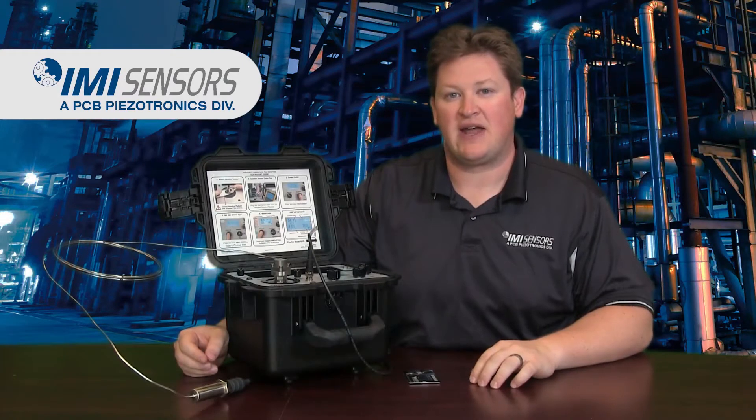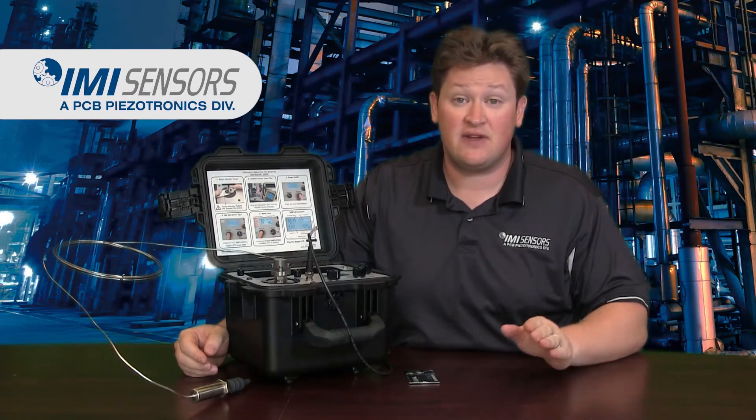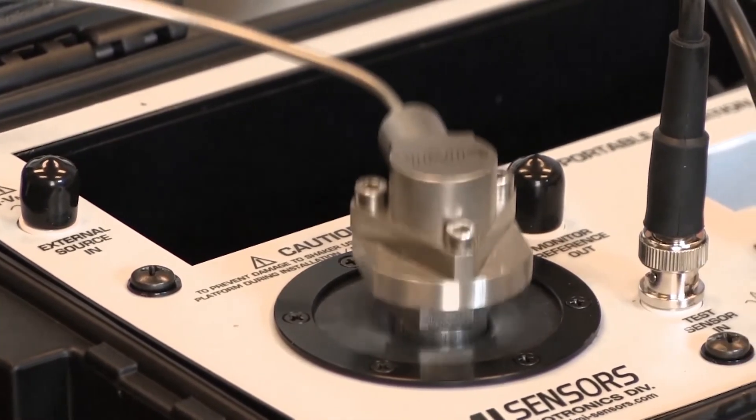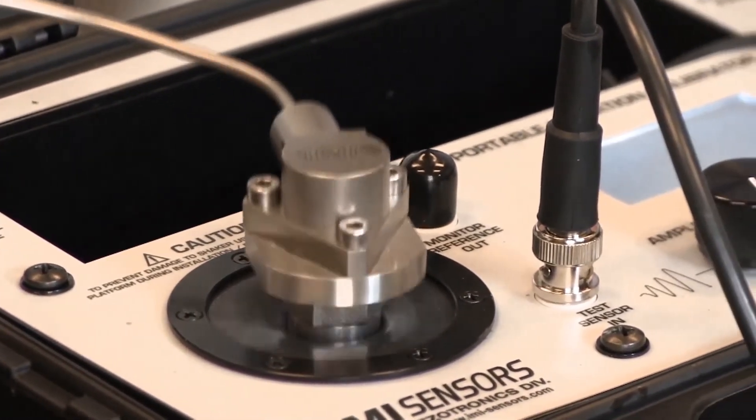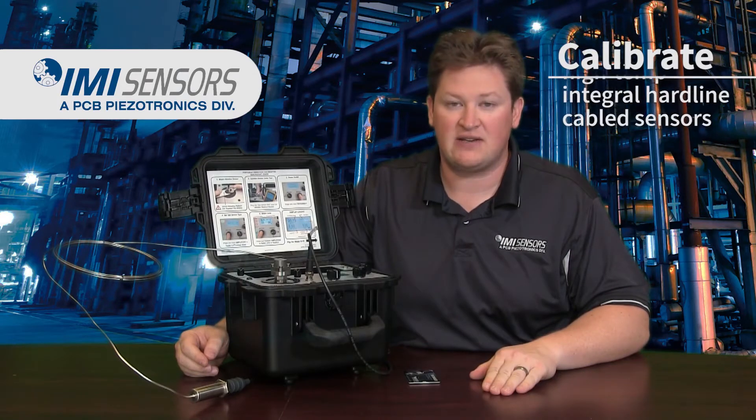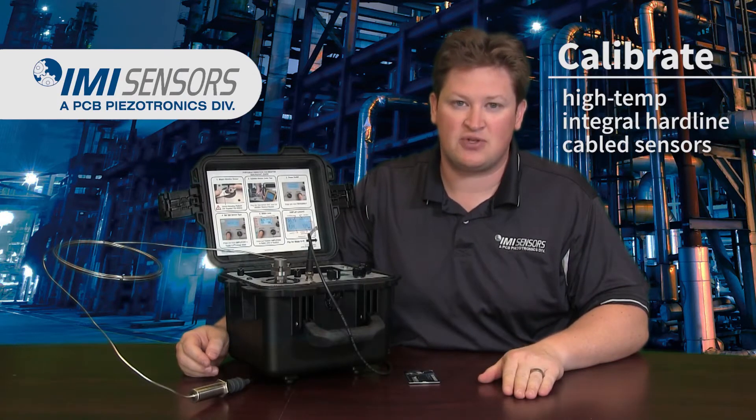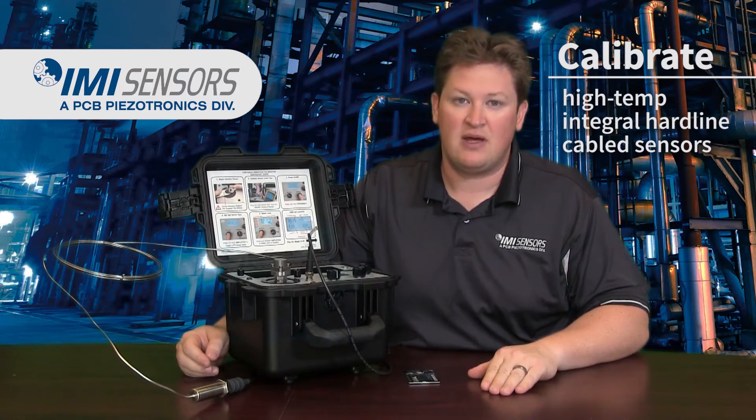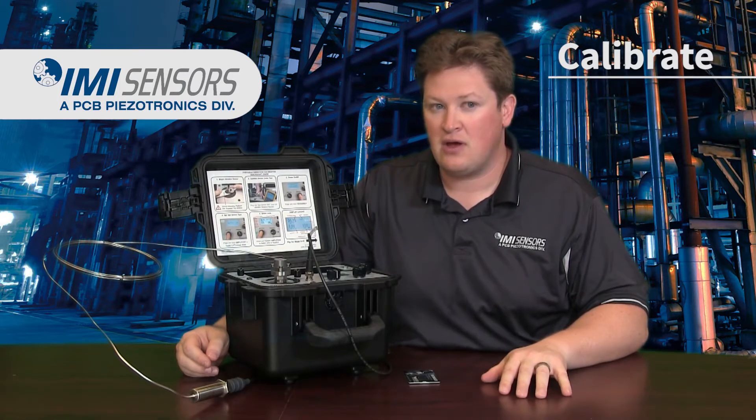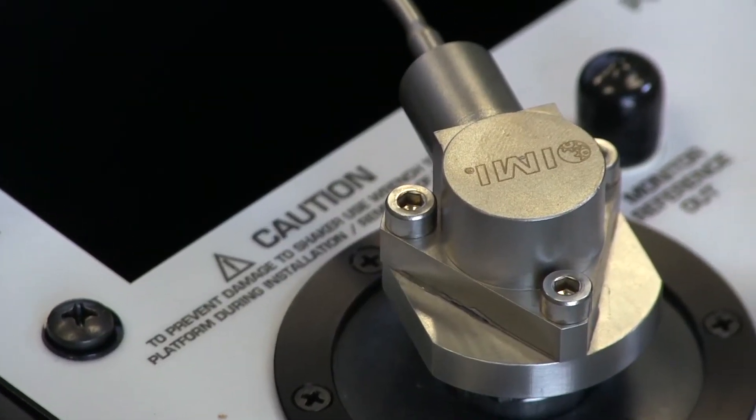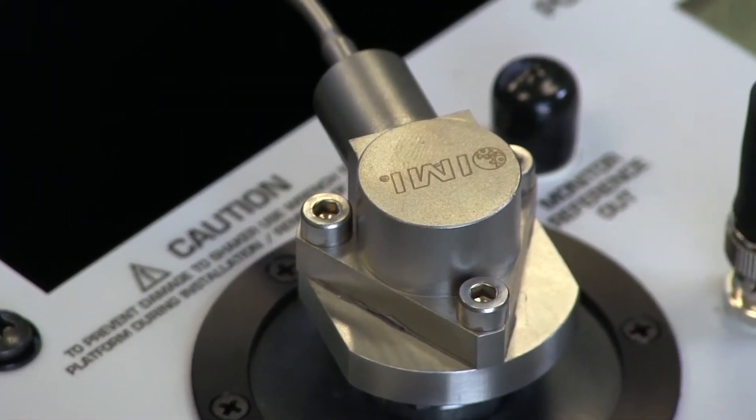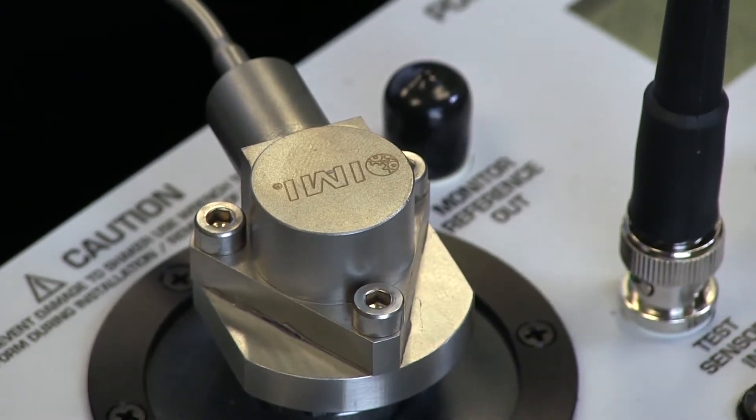Hi, my name is Mike Scott, Applications Engineer for PCB Piezotronics. In this video I'd like to show you how to calibrate some of the more challenging sensors that we see in the vibration field: high temperature integral hardline cable accelerometers or velocimeters that you find on gas and steam turbines or any high temperature rotating equipment. These are typically either four hole mount or three hole mount with supplied mounting screws in a triangular or square shape.